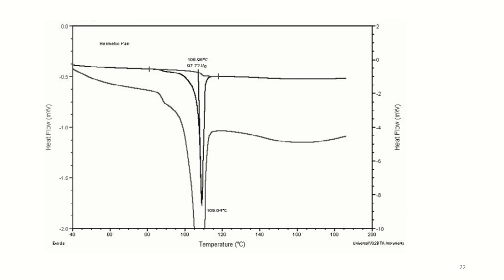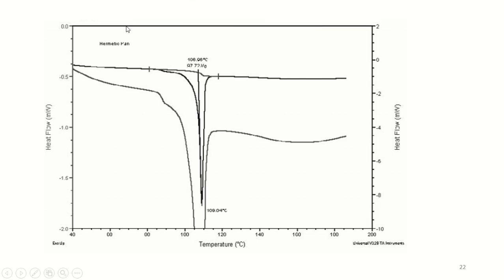The baseline shift from the beginning to the end of the melt is caused by the higher heat capacity of the liquid phase as compared to the solid phase. Because of this step, the most accurate way to integrate the peak is with the sigmoidal baseline. The most important information from this scan is that there is only a single melting peak, that is, one polymorph.